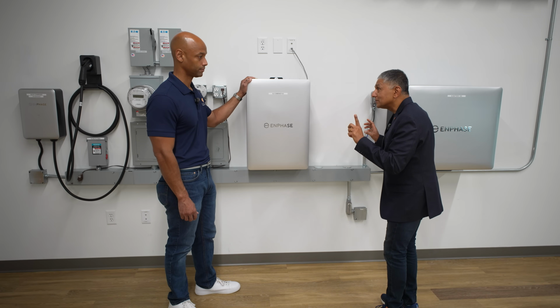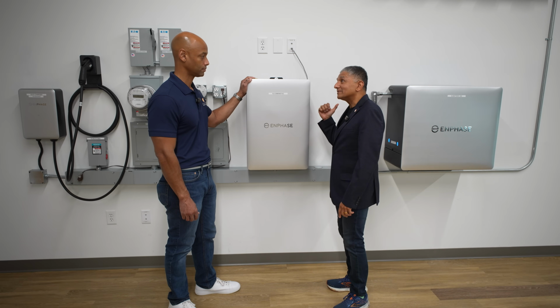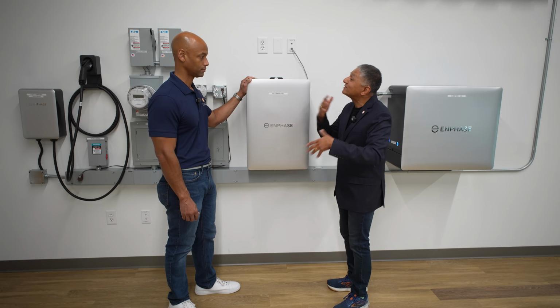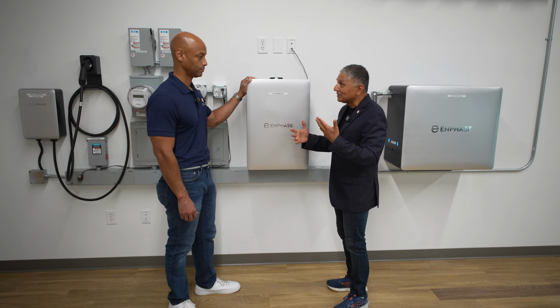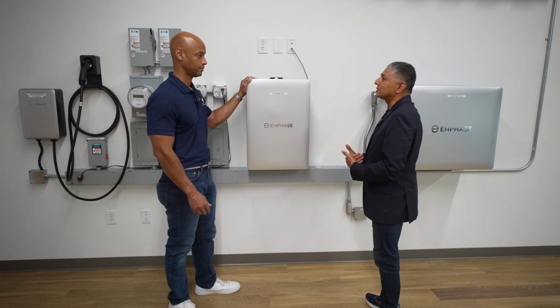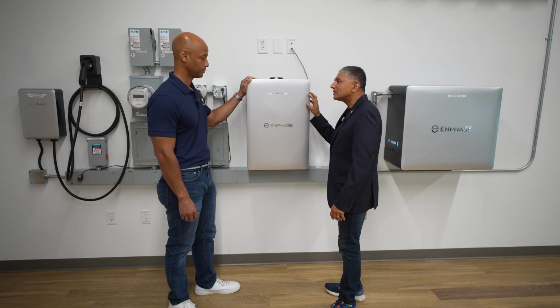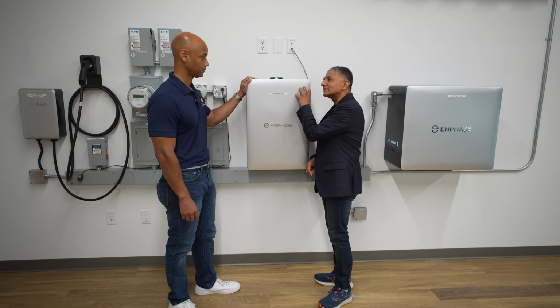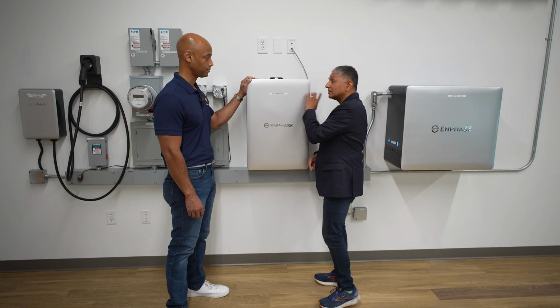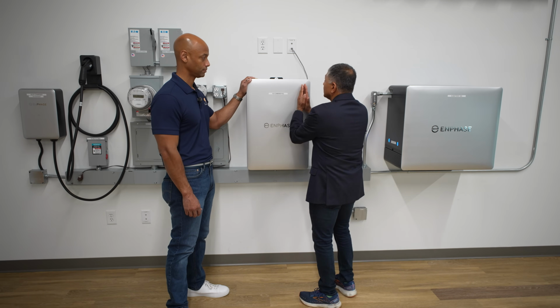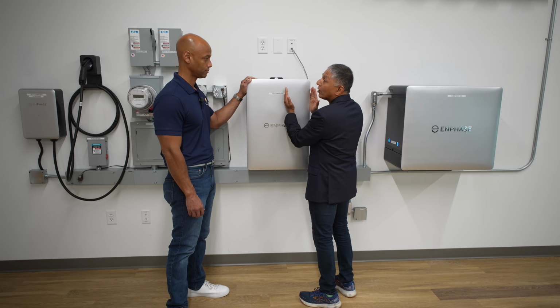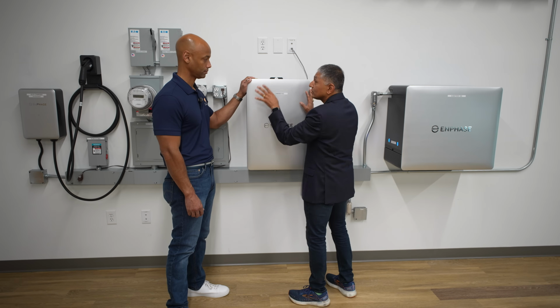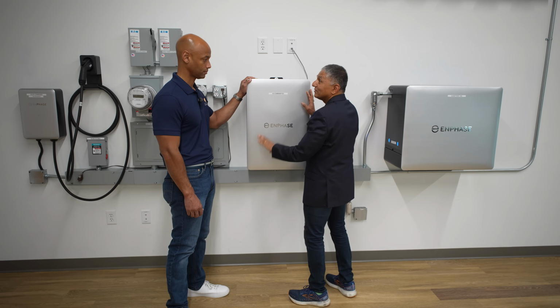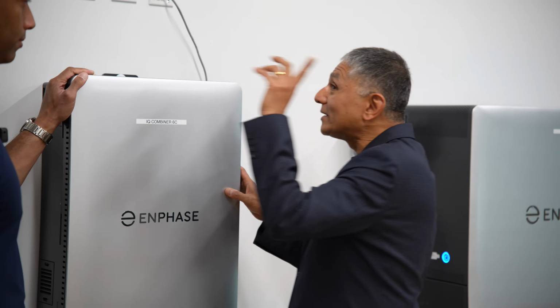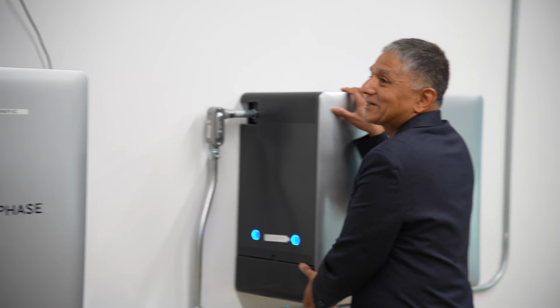But there was one problem. The problem was the loads were always connected. So the IQ8 in the morning would start waking up, starting to charge the battery, and then the loads would be present and the microgrid would collapse. But with the Combiner 6, what we have done is we have an isolation relay built in here. So the moment the battery collapses or the microgrid collapses, this relay opens. So the DER, the solar, the battery is all isolated from the load. So when the sun first wakes up, it doesn't see any load. So all the power that the solar is generating starts charging the battery.